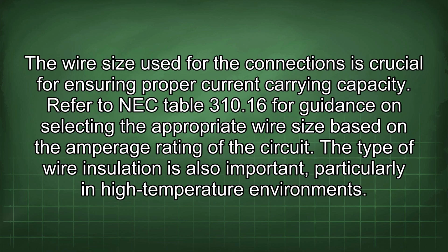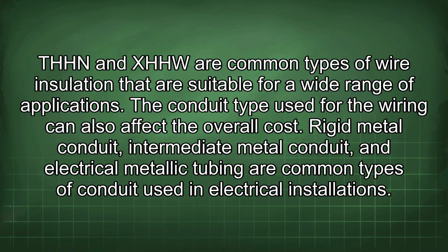The wire size used for the connections is crucial for ensuring proper current carrying capacity. Refer to NEC Table 310.16 for guidance on selecting the appropriate wire size based on the amperage rating of the circuit. The type of wire insulation is also important, particularly in high-temperature environments. THHN and XHHW are common types of wire insulation that are suitable for a wide range of applications. The conduit type used for the wiring can also affect the overall cost. Rigid metal conduit, intermediate metal conduit, and electrical metallic tubing are common types of conduit used in electrical installations.